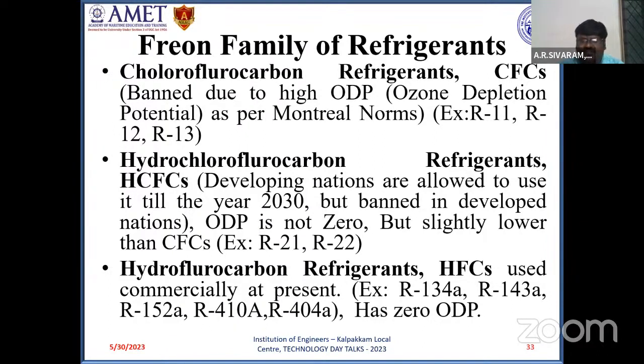The next family of refrigerant is hydrochlorofluorocarbon refrigerant, shortly denoted as HCFCs. Of course, this type of refrigerant is banned in developed nations, but developing nations are allowed to use it till the year 2030. This also has ozone depletion potential. HCFCs do not have zero ozone depletion potential. Now, gradually, HCFCs are phasing out, and they are being replaced by HFCs even in developing nations. A typical example is the phasing out of R22 and replacing R22 by R134A.